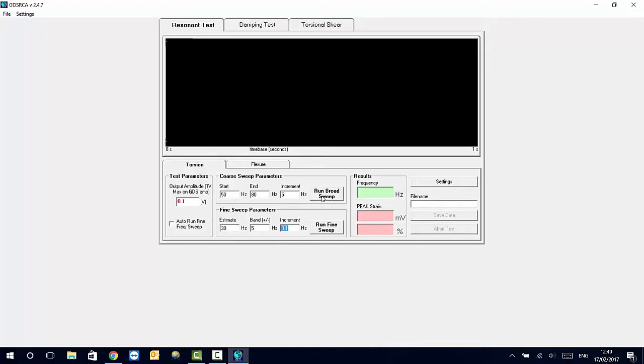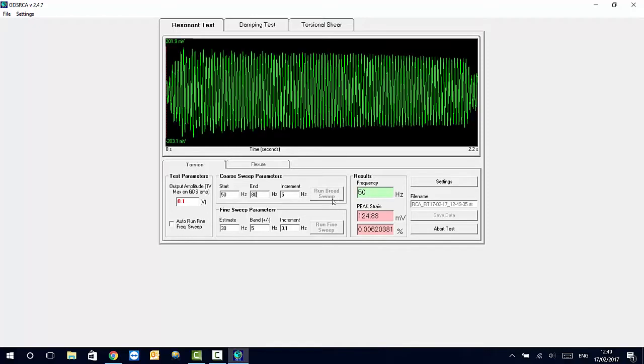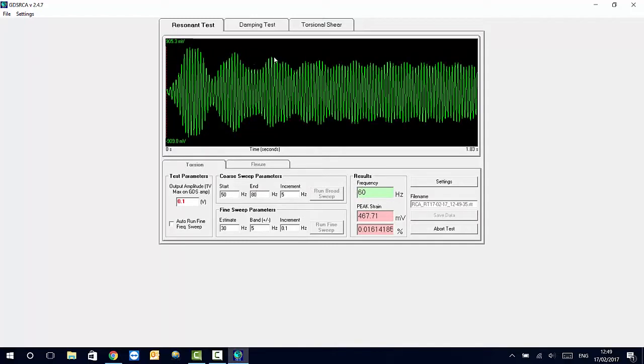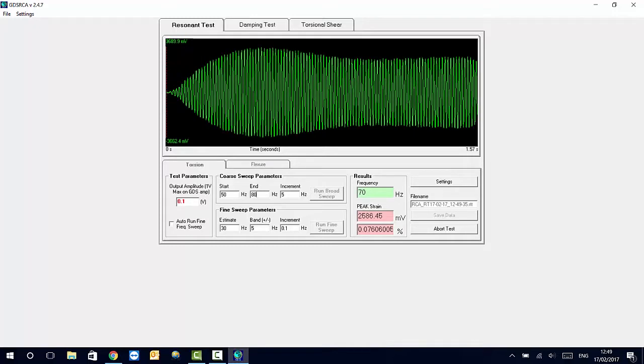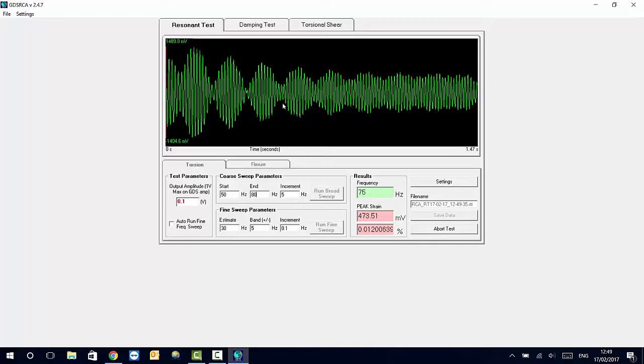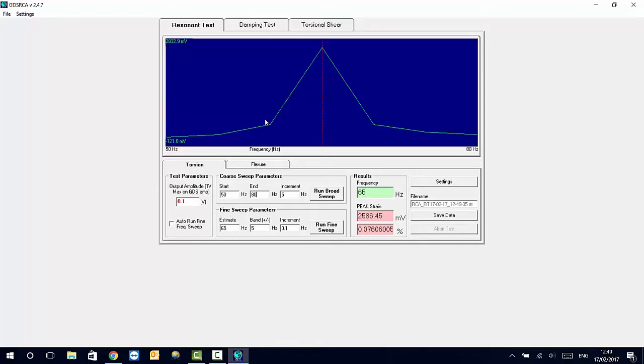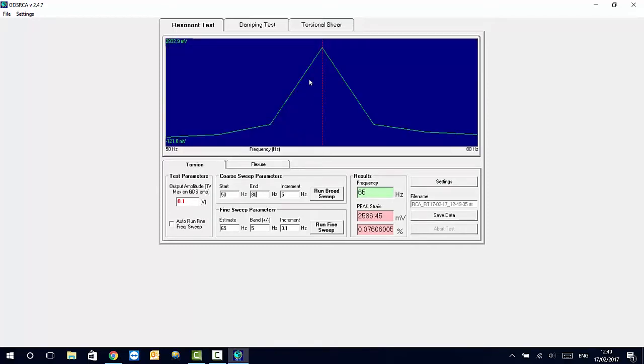So here we are going to run the test and while we do so we will see how our frequency readings are increasing in increments of 5 Hertz and we on the screen are also seeing the response of the accelerometer in terms of millivolts. There you go. So here we have found a close, a relatively close match for our response.